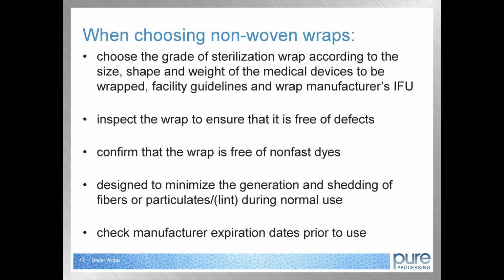When choosing and using non-woven wraps, sterile processing personnel should choose the grade of sterilization wrap according to the size, shape, and weight of the medical devices to be wrapped, the guidelines within the healthcare facility, and the wrap manufacturer's written IFU. Inspect the wrap to ensure that it is free of defects that could have an adverse effect on the performance of the material. Then confirm that the wrap is free of non-fast dyes and is designed to minimize the generation and shedding of fibers or particulates during normal use. Check disposable wraps for manufacturer expiration dates prior to use to avoid reduction in the packaging's ability to perform at optimal standards.